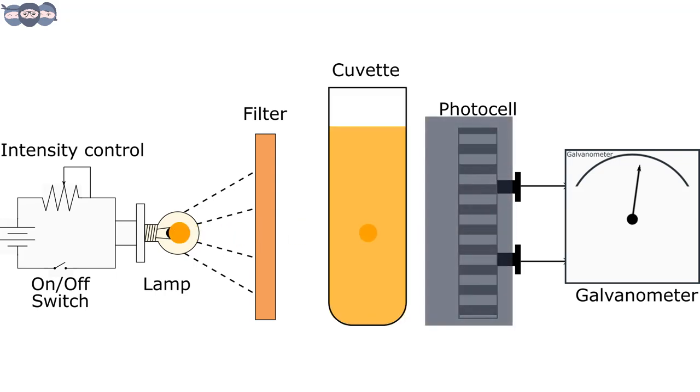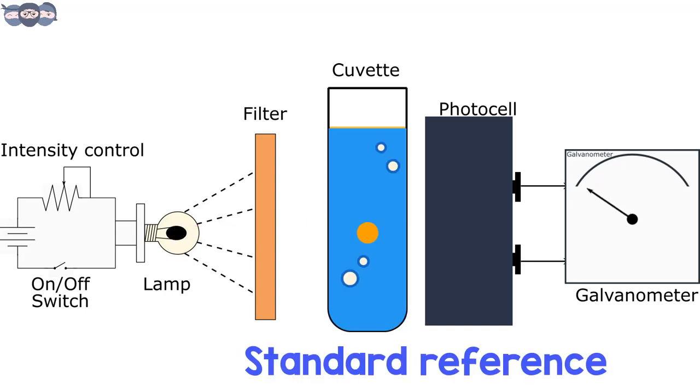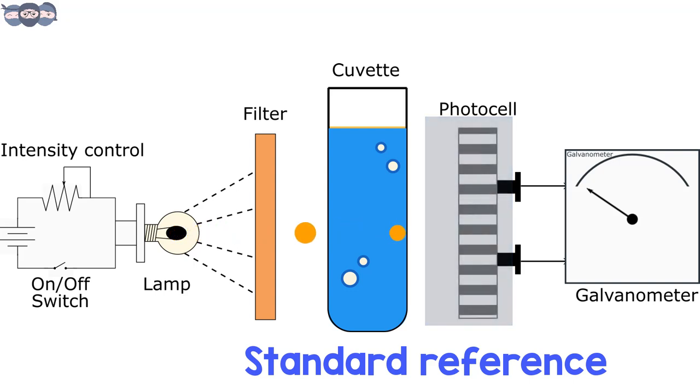Initially, the detector is darkened and galvanometer is adjusted mechanically to read zero. Now, a reference solution or blank solution is kept in the sample holder. The light transmitted from this solution is made to fall on the detector. The intensity of light source is adjusted using the intensity control circuit such that the galvanometer shows 100% transmission.